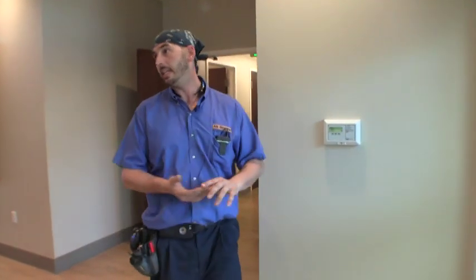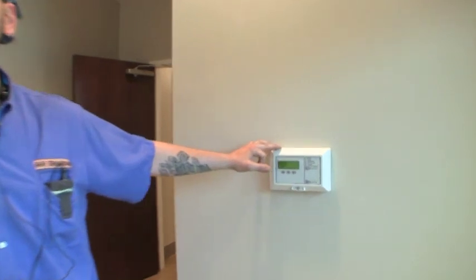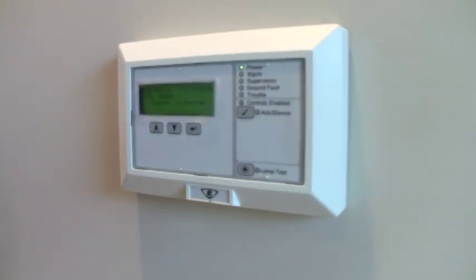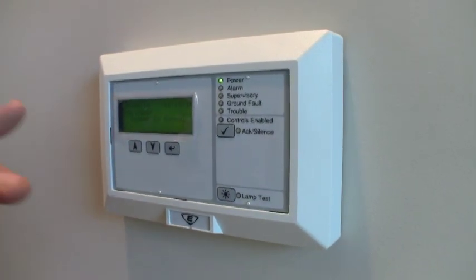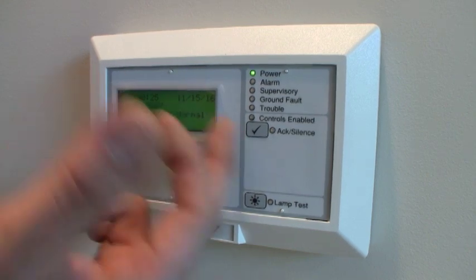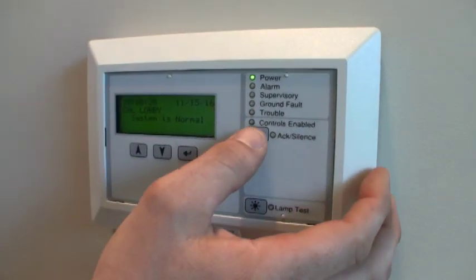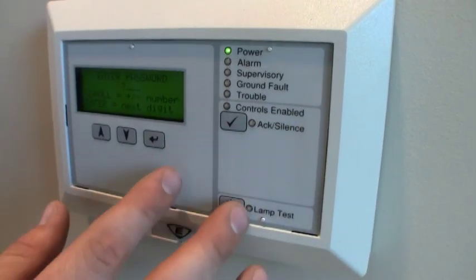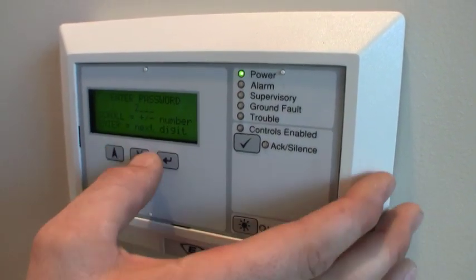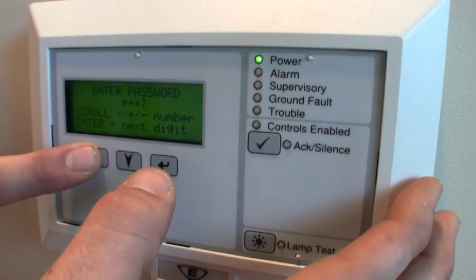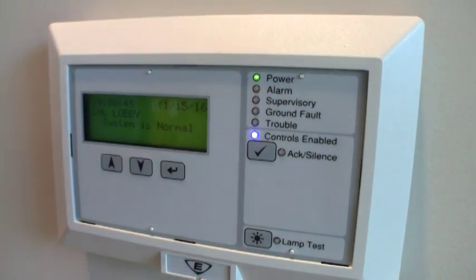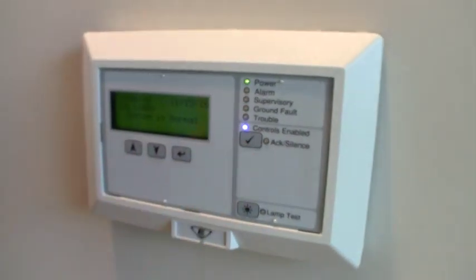We are now in the CHL building of Moran's Park. This is a different type of panel — this is our remote annunciator. This is most times what you would look to to see the status of the system. Right now, the system is normal. If an alarm or anything comes through onto the panel, it will be displayed as a direct duplicate here, and you can acknowledge and silence the panel from here. The password is 2222 — that gives you the ability to silence an alarm or supervisory.